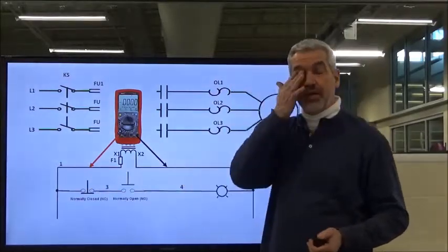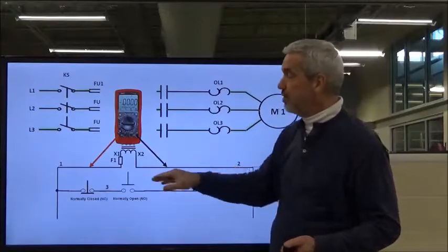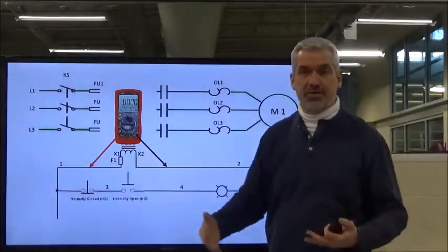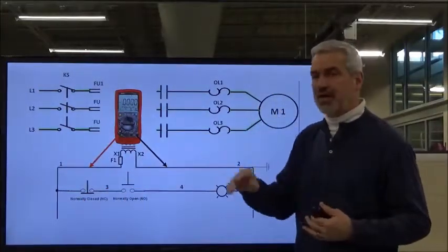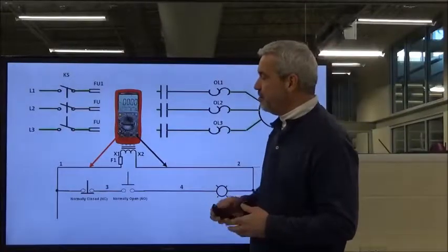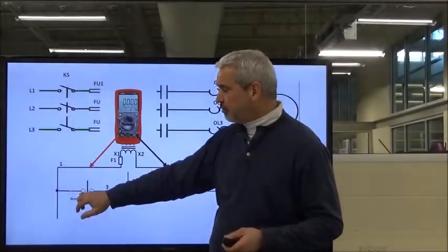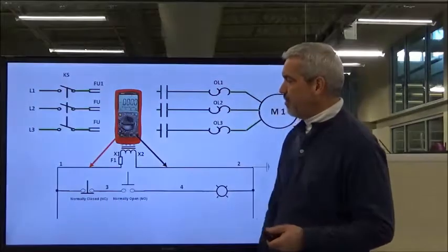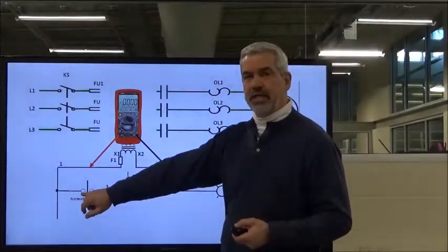And your schematics will tell you this, particularly on the construction. They'll show you where all the junction boxes are and all these termination points, if they're midway or something like that. But what we want to do is put our voltmeter right here on the incoming side to this normally closed switch.